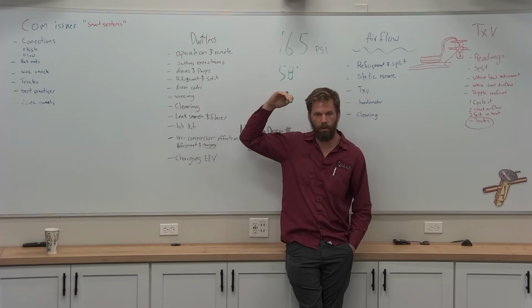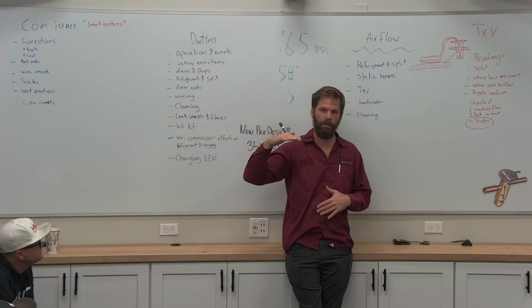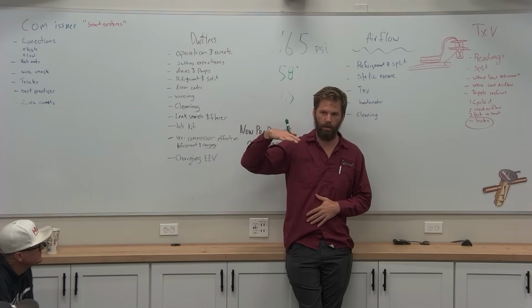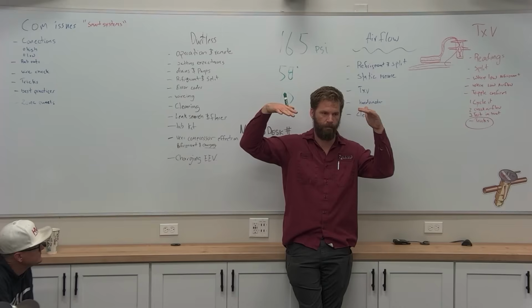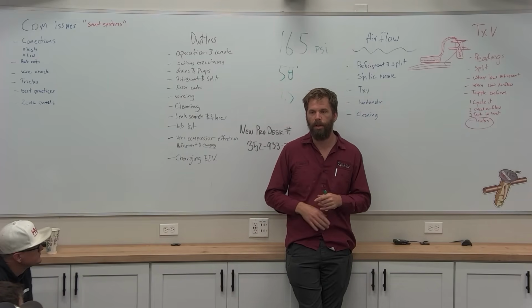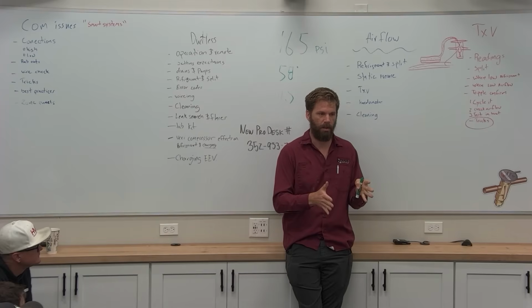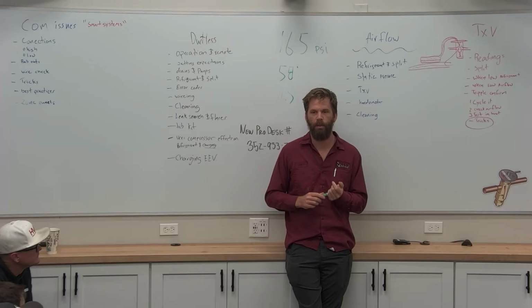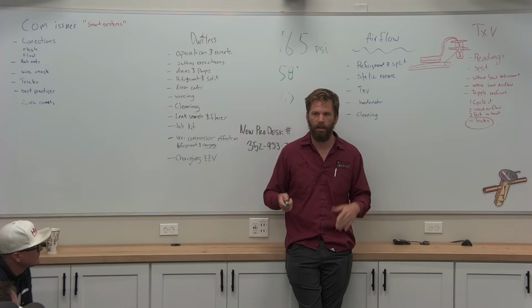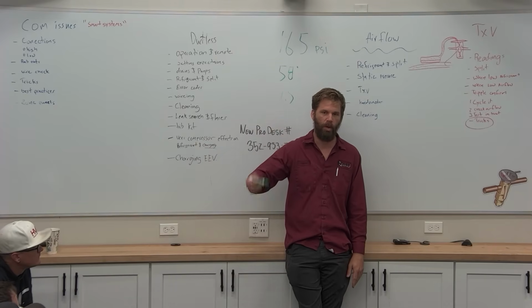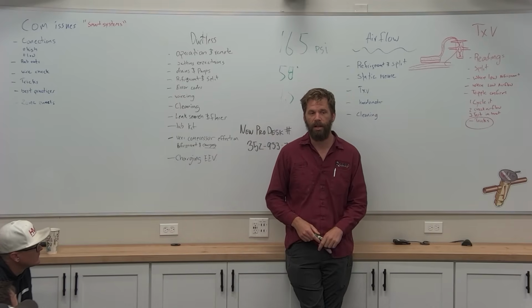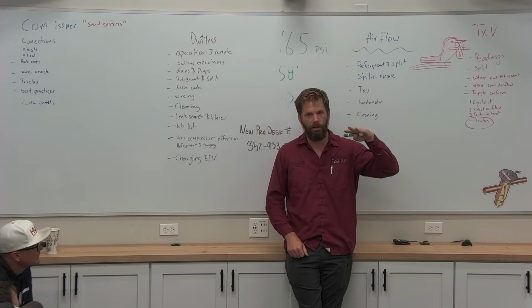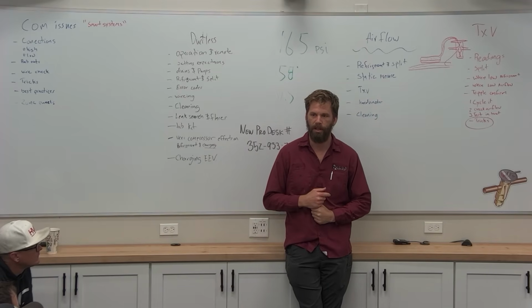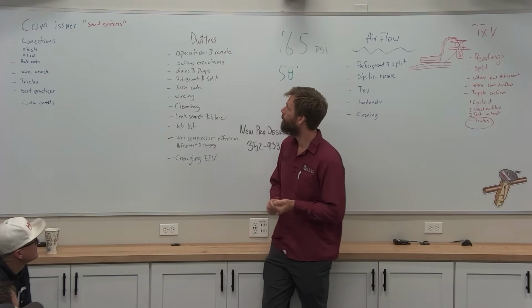If you're low on refrigerant, they will also bring the compressor down. It'll kick on really hard, it'll come down really low. As soon as it gets to a very low point, it slows the compressor down and lets the refrigerant levels come back up. If you don't see that happen, you won't know that you're low on refrigerant, watching it all the way from the starting point through. So just remember, with a variable speed compressor, you want to turn everything off, turn it back on, and listen. You hear your compressor come on, you'll hear it rev up all the way, and then sometimes you'll catch it slowing back down because it's got a problem. Maybe it goes out on high head and it revs down just to try to keep it from high pressure on the other side. So, variable speed compressors.